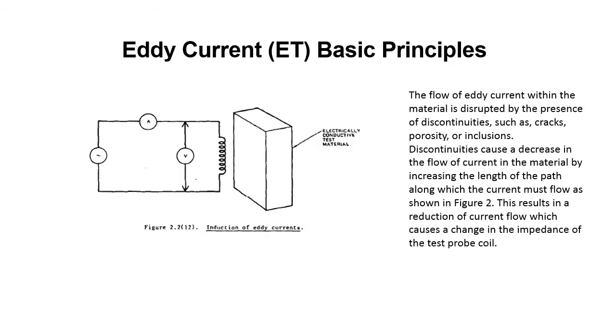Eddy Current Testing Basic Principles. The flow of Eddy Current within the material is disrupted by the presence of discontinuities such as cracks, porosity, or inclusions. Discontinuities cause a decrease in the flow of current in the material by increasing the length of the path along which the current must flow, as shown in Figure 2. This results in a reduction of current flow which causes a change in the impedance of the test probe coil.